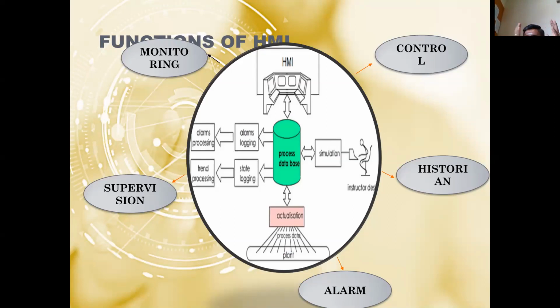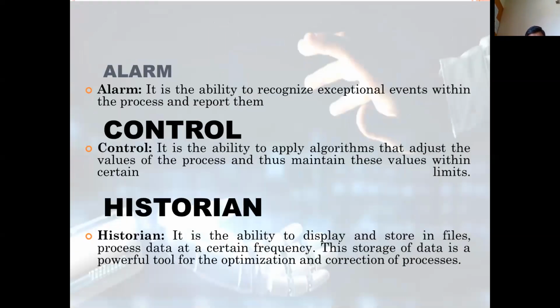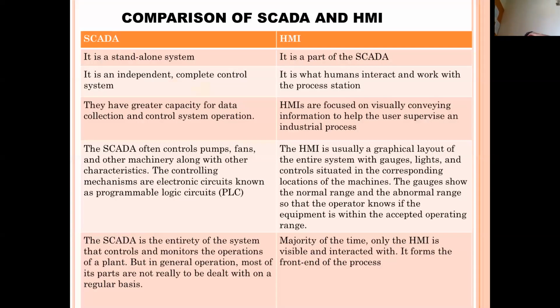And the historian: what are the trends happening? What are the things happening? Logging, that is, all these trends will be stored in a document. So there's a difference between the SCADA and the HMI. As I said, the HMI is a part of the SCADA, whereas the SCADA is a standalone system, independent and complete.